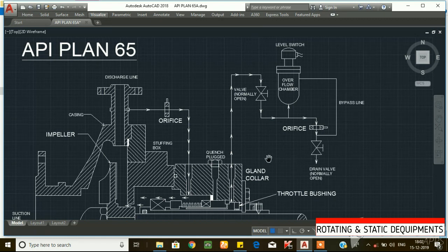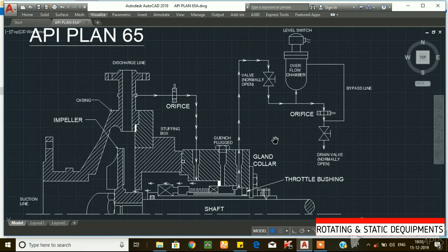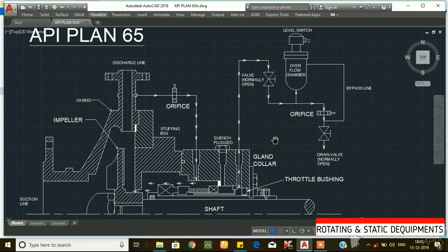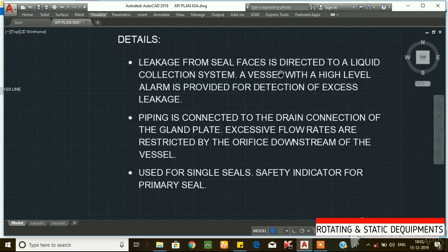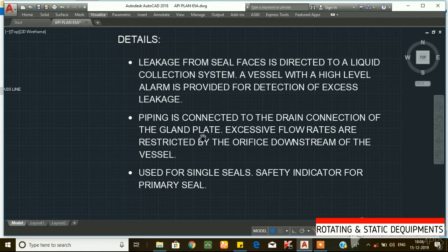This is the API plan 65. This plan is suitable when you have a minor seal leak or a mechanical seal leak while the pump is running. Excess leak liquid needs to be managed while keeping the pump running. Leakage from seal faces is directed to a liquid collection system. A vessel with a high level alarm is provided for detection of excess leakage. Piping is connected to the drain connection of the gland plate. Excessive flow rates are restricted by an orifice downstream of the vessel. Used for single mechanical seal and as a safety indicator for the primary seal.